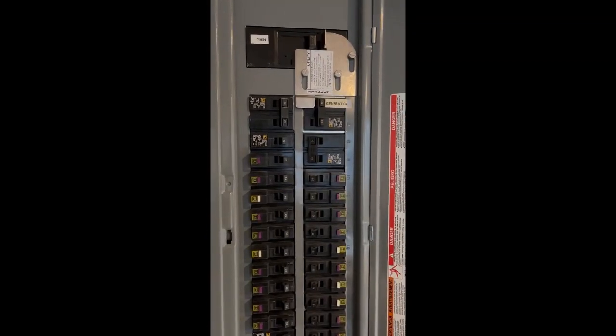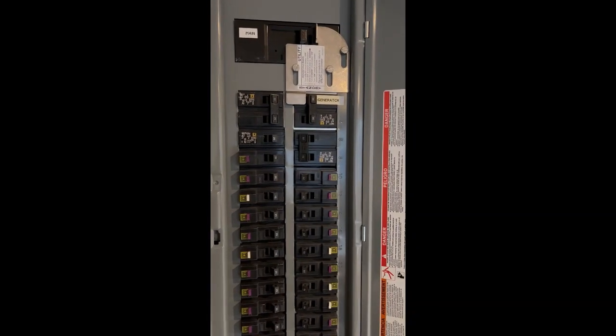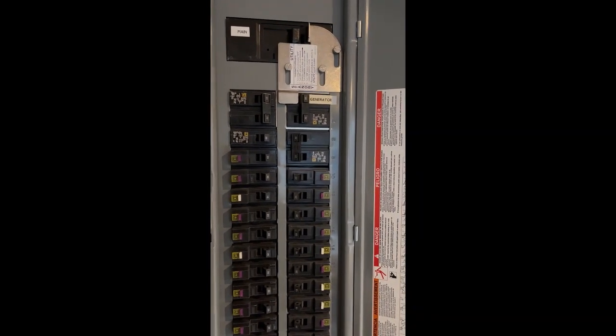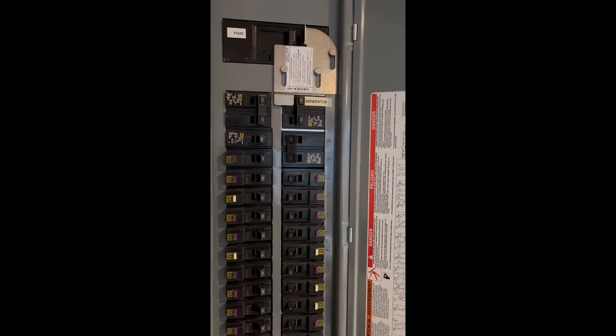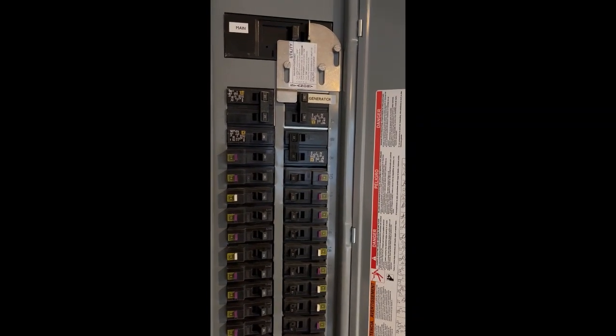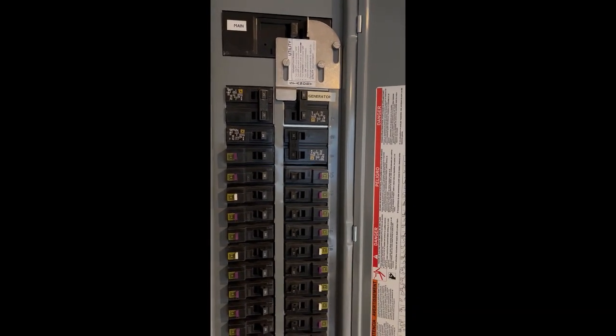Step 6 would be to turn the generator breaker on. This is after you shut the main off, moved the generator outside, hooked up the generator cables, and come back down here.